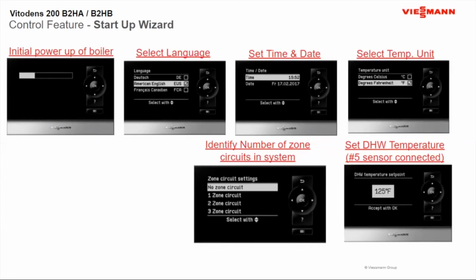So now this is the way you would get the boiler today. All that stuff I was showing you was when this boiler first came out. Now, when you start up the boiler, the initial power up bar still comes up, so you see it power up. First thing it's going to ask you is, do you want it in American English? You're just going to hit OK. Set your time and date. Remember the importance of your time and date. And then at the same time, let's set your Fahrenheit and hit OK.